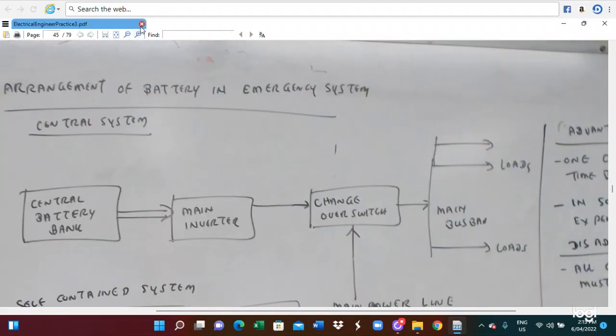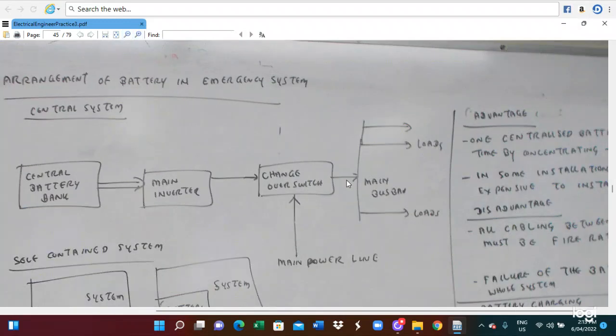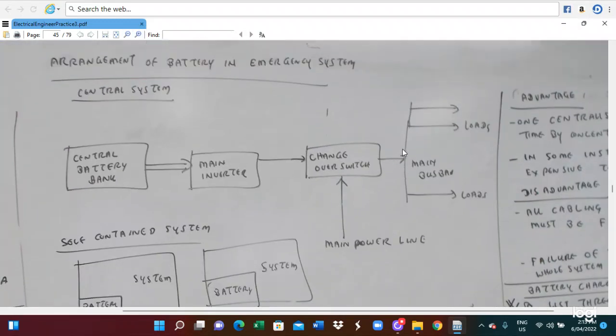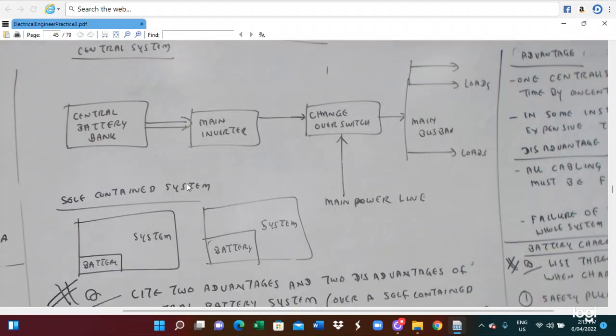So this is for the arrangement of batteries in an emergency system. There is a central system. The central system is a central battery bank, which is supplied to the main inverter, and then we connect it to the changeover switch. It is also connected to the main power line, and here you can also connect it to the load. So this is a central system.